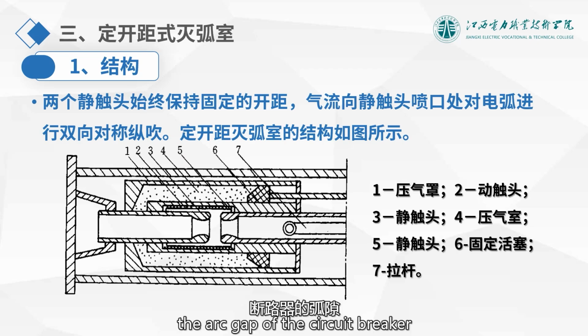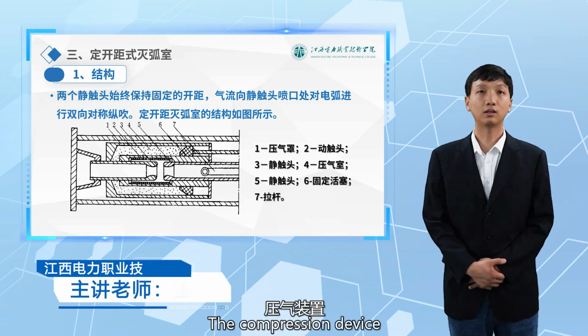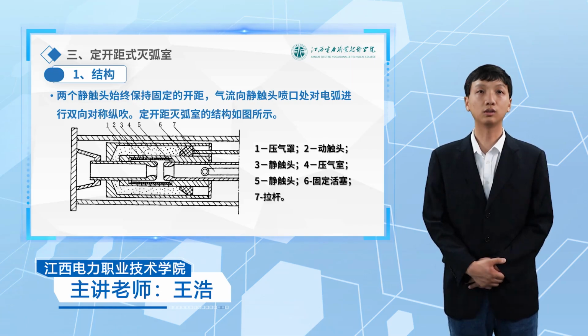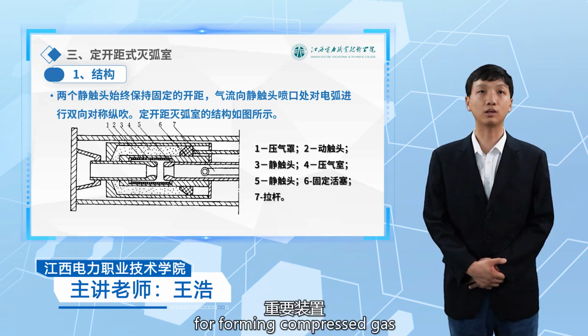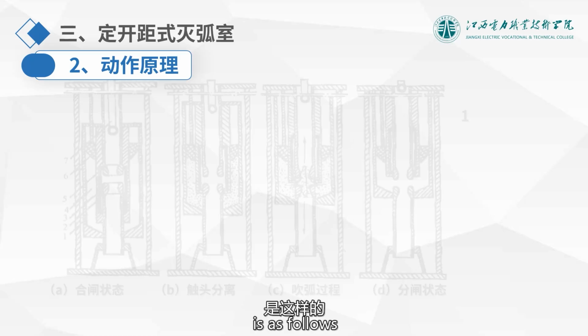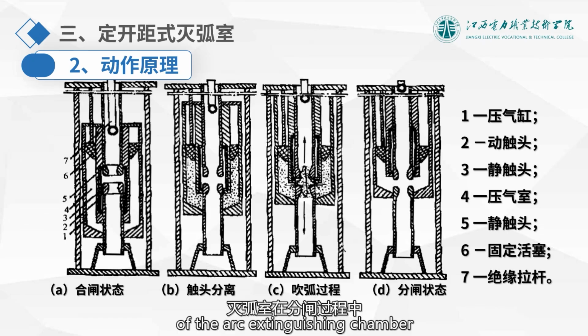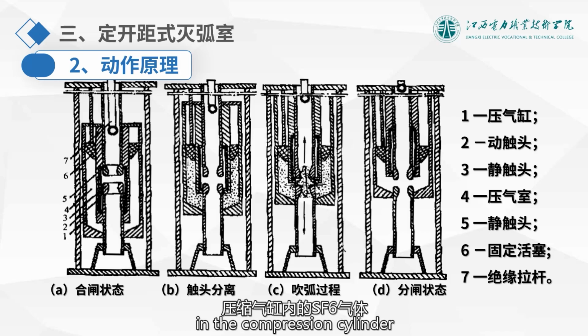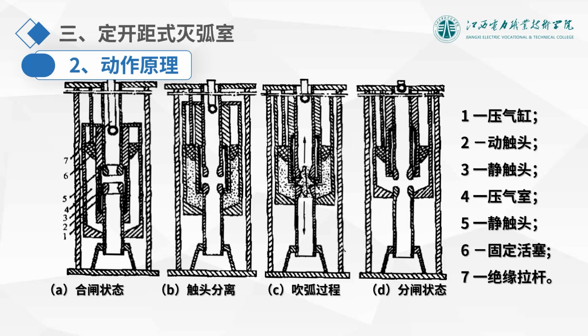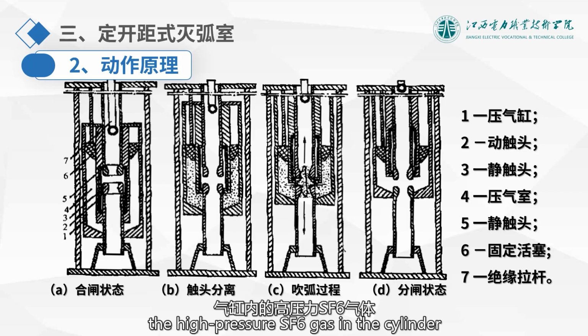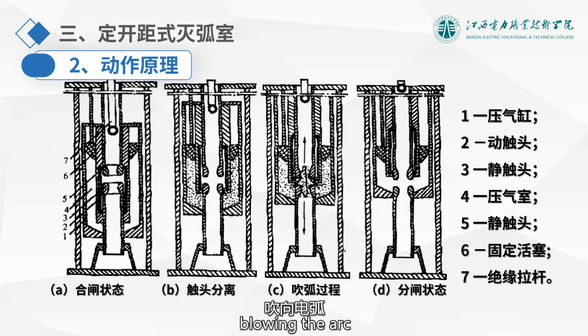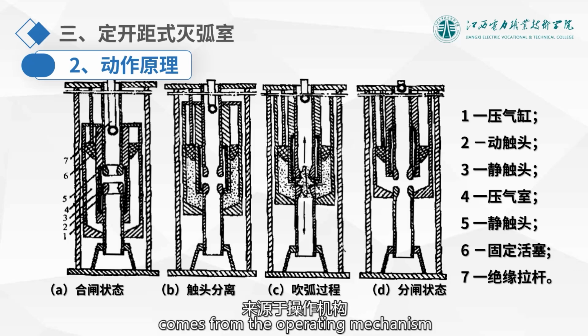When opening, the arc gap of the circuit breaker is maintained at a fixed gap by the two stationary contacts. The compression device includes a compression chamber, compression cover, fixed piston, etc., which is an important device for forming compressed gas. Its operating principle is as follows. During the opening process of the arc extinguishing chamber, the gas cylinder is moved by the moving contact rod, compressing the sulfur hexafluoride gas in the compression cylinder, creating high pressure. When the moving contact rod moves to the nozzle and opens it, the high-pressure sulfur hexafluoride gas in the cylinder is expelled from the nozzle, blowing the arc, extinguishing it. Throughout the process, its arc-blowing energy comes from the operating mechanism.